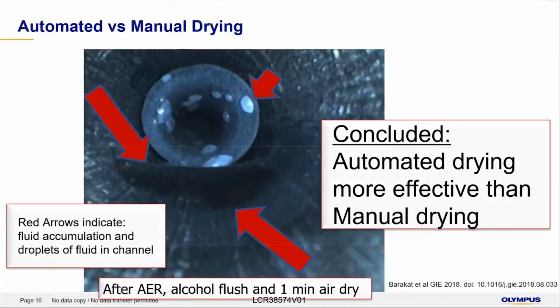What this tells us is that there is widespread lack of compliance with the guidelines. In fact, Thaker commented it was shocking to see that so few of the sites were using forced air drying. And I think part of the reason why this hasn't been integrated as well as it should have been into the procedure is the widespread belief that if the automated endoscope reprocessor, the AER cycle, has an alcohol flush and forced air dry at the end of the cycle, that was adequate to meet the manufacturer's instructions indicating thorough drying before storage.